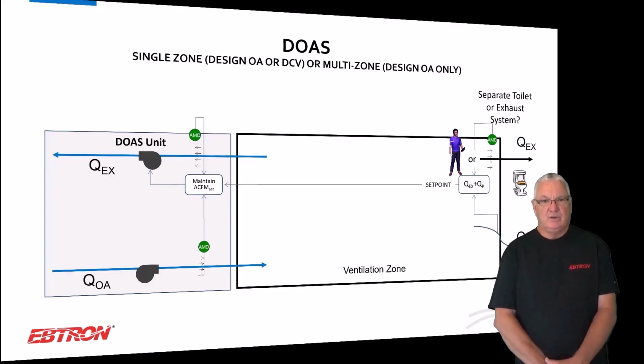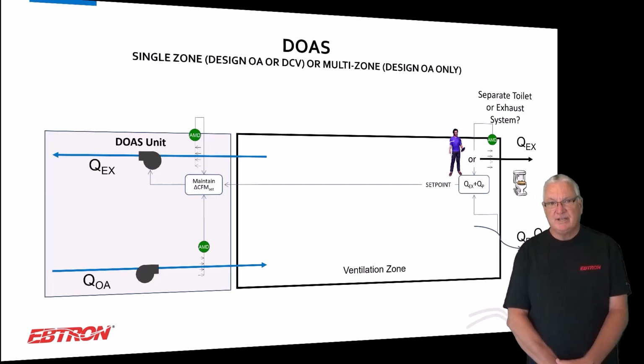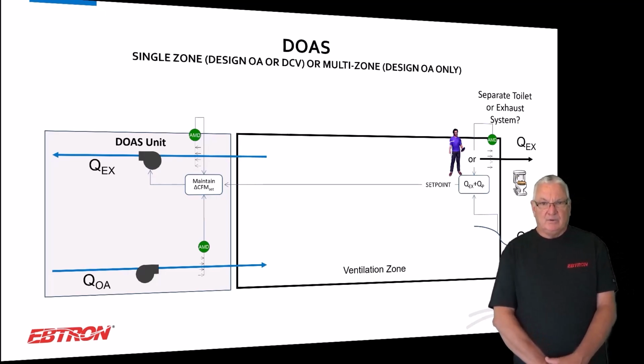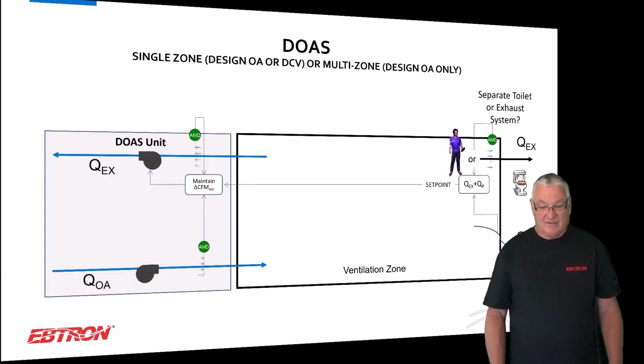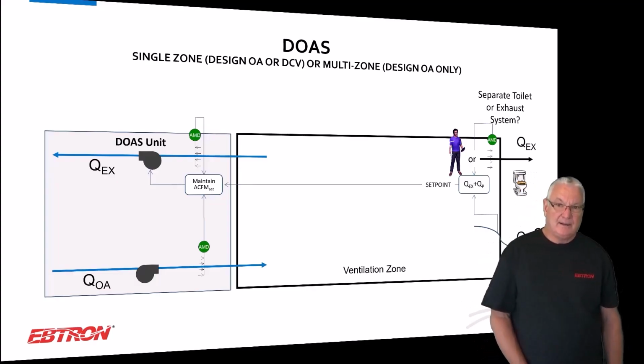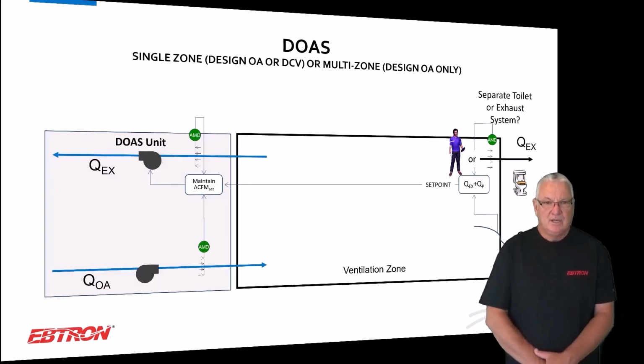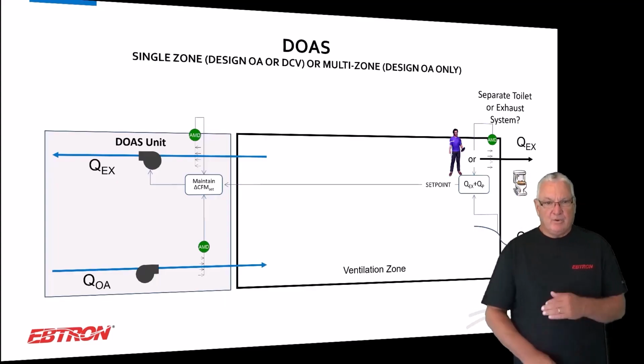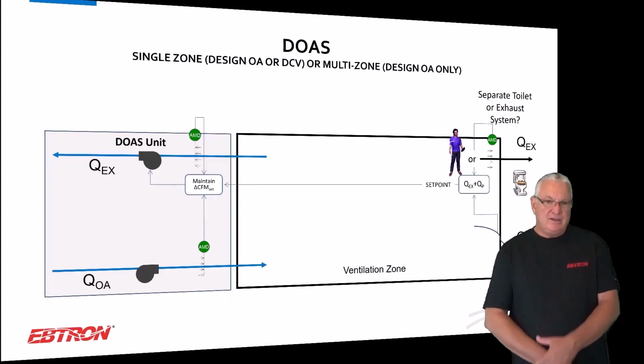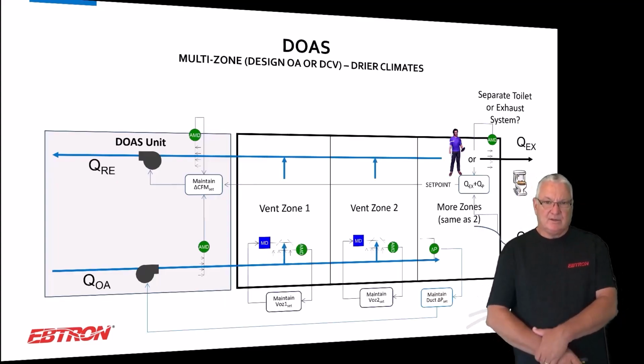So, if it's a simple DOAS unit and you're just looking at treating everything like a single ventilation zone, I think you can do this if it's design outdoor air, not DCV on multi-zone. But if it's multi-zone, you got to really think about it differently, which I'll get to. You want to maintain that flow differential, and you do want to maintain your set point as well, okay?